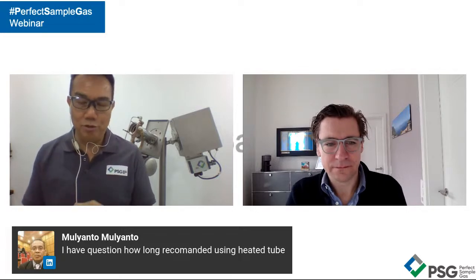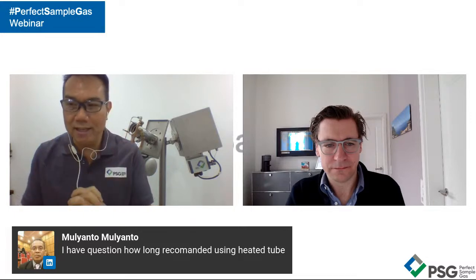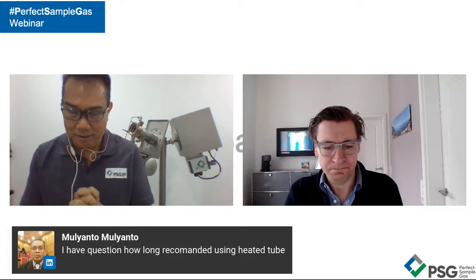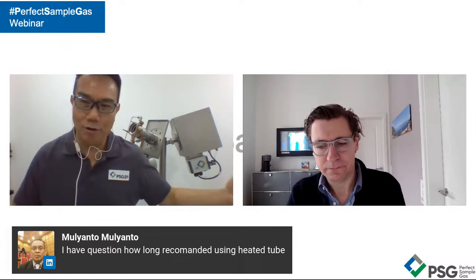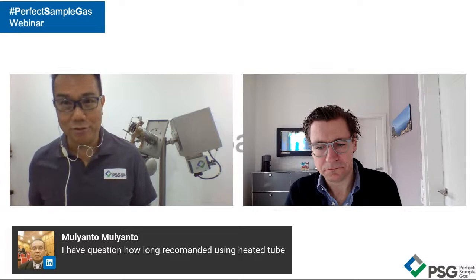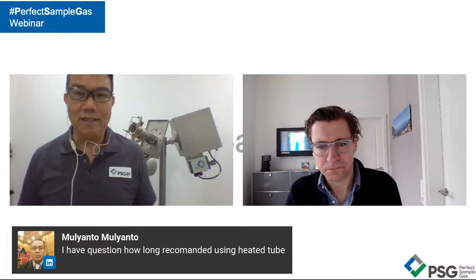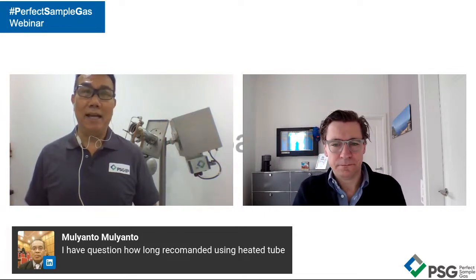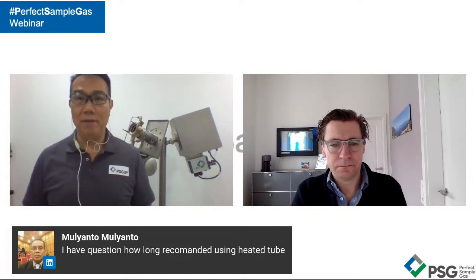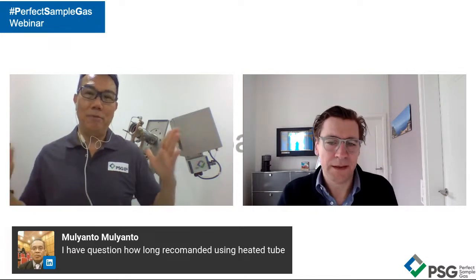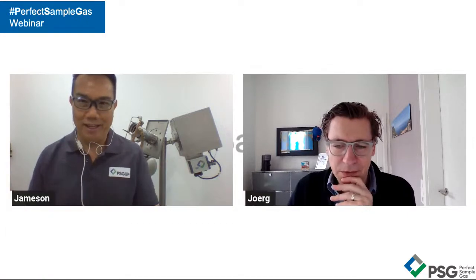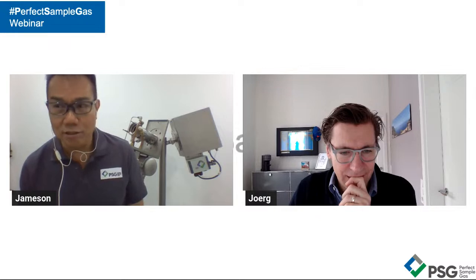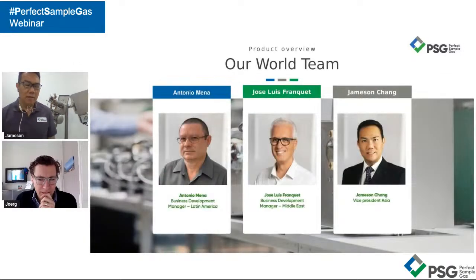As long as possible. Theoretically, the heated tube can reach the middle of the stack, but we have to ask ourselves what is practical. If a stack is 6 meters in diameter in a coal-fired plant, and you put a tube in 3 meters, there will be resonance due to the high velocity inside a stack of that size, as tall as 80 to 90 meters, with a velocity of at least 15 meters per second going upward. A 3-meter heated tube will resonate and break at the joint. So a rule of thumb is that it must be at least 0.5 meters from the wall. That means if you can't reach half the radius, reach at least a third of the length. Yeah, that's a good rule of thumb.